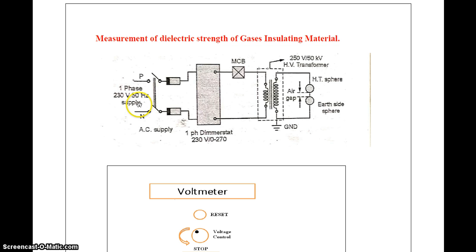Then a single phase 230 volt 50 Hz supply, phase neutral AC supply, is given to the primary side of the Dimmerstat. The Dimmerstat varies voltage from 0 volt to 270 volt, which goes to the primary side of the step up transformer. The main function of the step up transformer is that output voltage is greater than input voltage. Then the MCB, that is miniature circuit breaker, is used to open or close the circuit with the help of contacts. A circuit breaker consists of two contacts, a fixed contact and a moving contact.